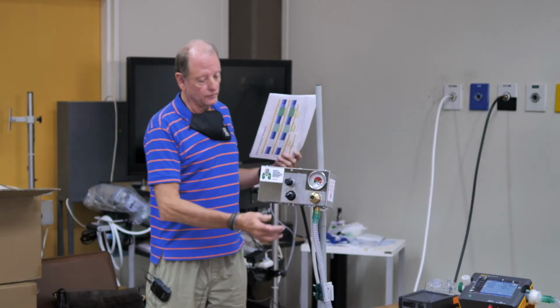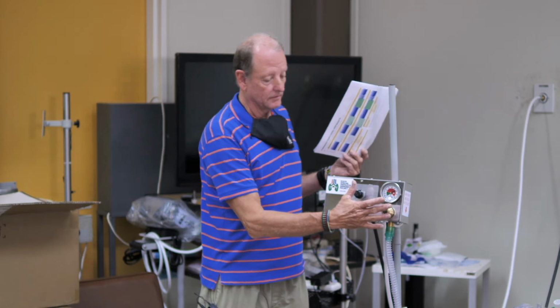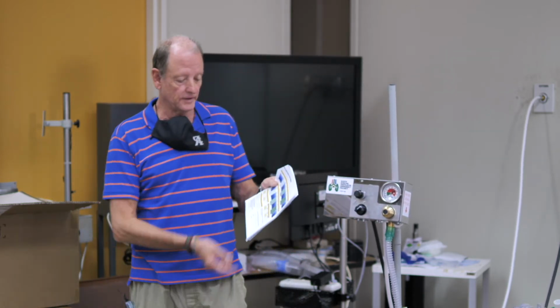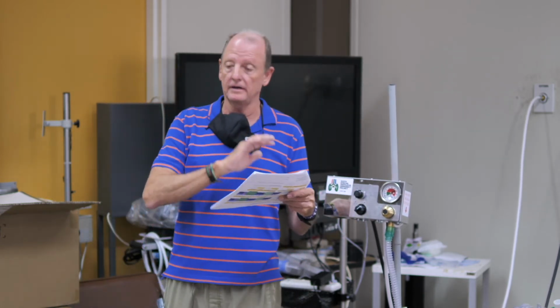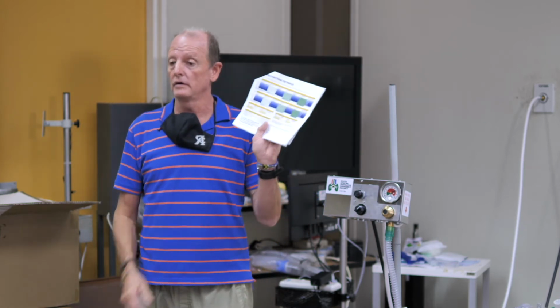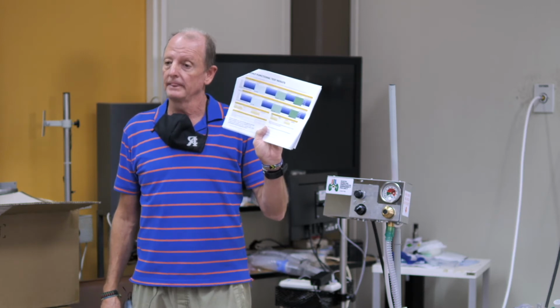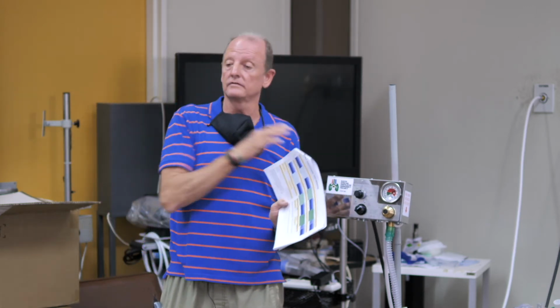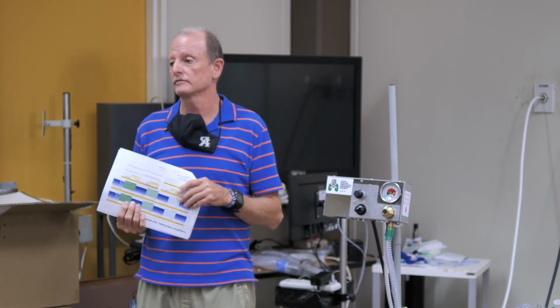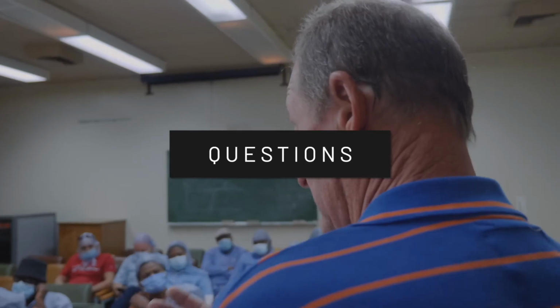We've checked the gauge, we've checked the on-off switch, we've now checked all the percentages. Once it's finished and you're happy that everything's silent, that has to be logged onto the SAVE-P website so that this unit is recorded as having had a 3 monthly check. Even if it hasn't been used, please just do it. Do those checks that are necessary. All right. That is as simple as it is. That's it. Questions?